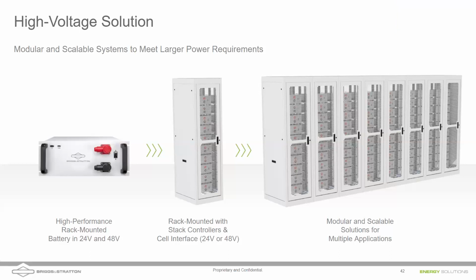Yeah, so they're 4.2 kilowatt hours each, and they're either 24 or 48 volts. Unlike our PHI, AmpliPHI, and SimpliPHI batteries, which run in parallel, these are designed to run in series. That allows us to get high voltage battery stacks that can work with inverters like the Sol-Ark 30K or the Sol-Ark 60K, which you'll see at RE+, matching the high voltage battery inputs those systems need. Typically these are used in three-phase 480 volt systems for commercial purposes. We can go up to 1180 volts with these stacks. As Daniel said, these run in series, and there's a stack controller there to make sure the system is properly maintained. So if you're interested in larger scale applications, we have a whole division that handles that.